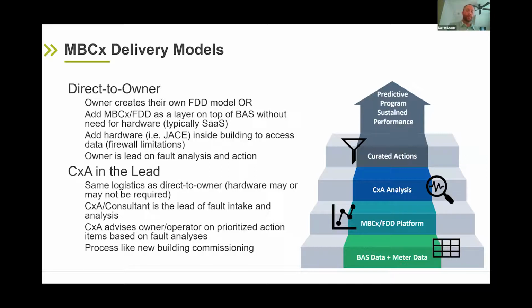The platform where a fault detection provider comes in with software as a service is typically a software-as-a-service arrangement. It could be for a year, multiple years, or months, depending on what the provider and owner agree to. We've seen instances where hardware is necessary inside the building, which could be for firewall limitations or the nature of a legacy building automation system. This matters because hardware is more physically intrusive, more time intensive to deploy, and more costly. Putting in a Jace is certainly more expensive than just grabbing data from a building automation system with a software patch on a VPN or on the owner's server.